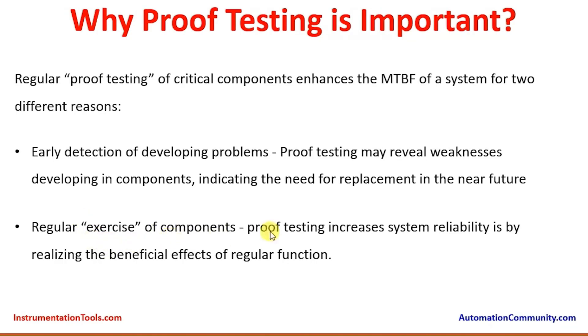The second reason is regular exercise of components. Proof testing increases system reliability by realizing the beneficial effects of regular function. The testing ensures that reliability is increased because during proof testing any hidden failures are revealed, so that the Safety Instrumented Systems are always made available to act in case of any emergencies or hazardous conditions.